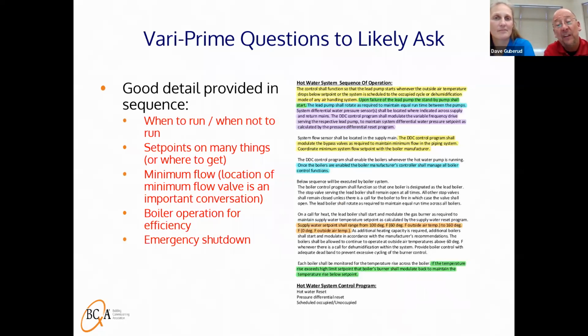This sequence of operation actually provided considerably more detail than the design build one that we showed earlier. It indicated within the sequence when the system should actually start. It provided the temperature set point values for the outside air reset schedule to the heat exchangers. But one thing it didn't mention or speak to as clearly is minimum flow. But this is a point again that we have on our pet list, if you will, where is the location of this minimum flow control valve?